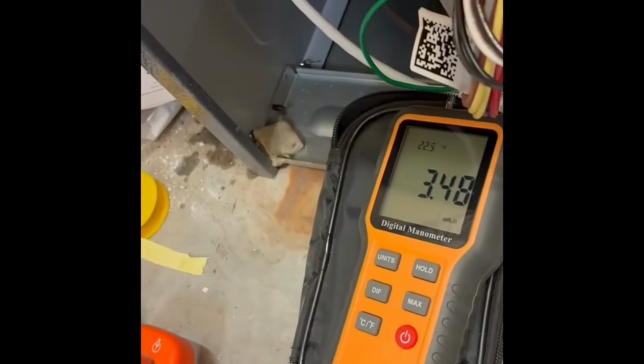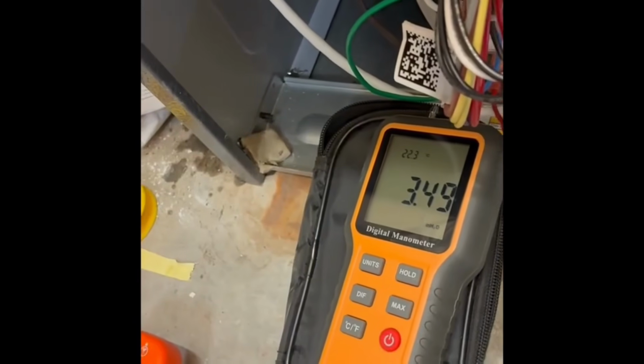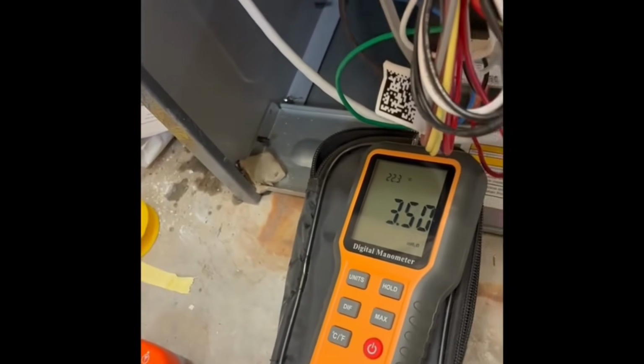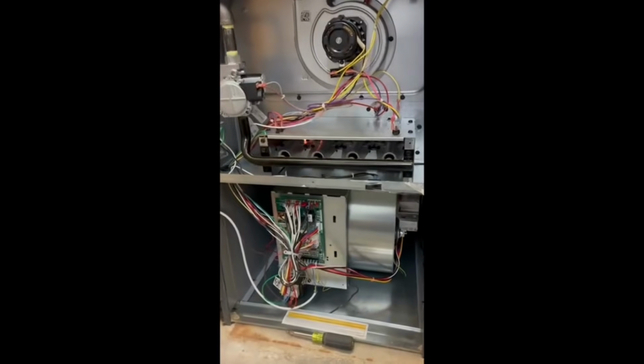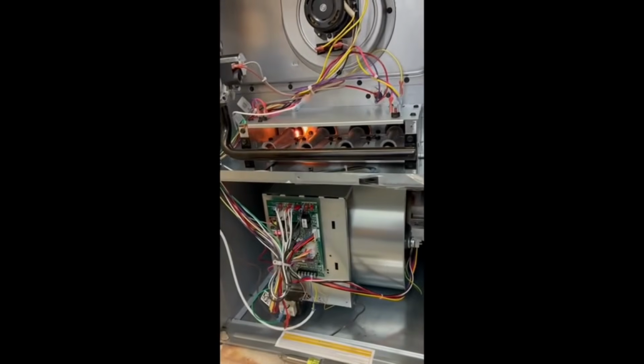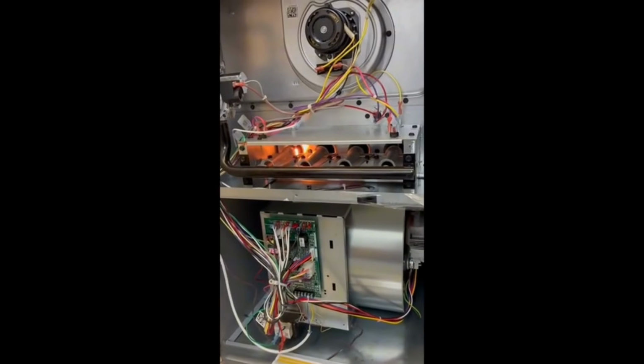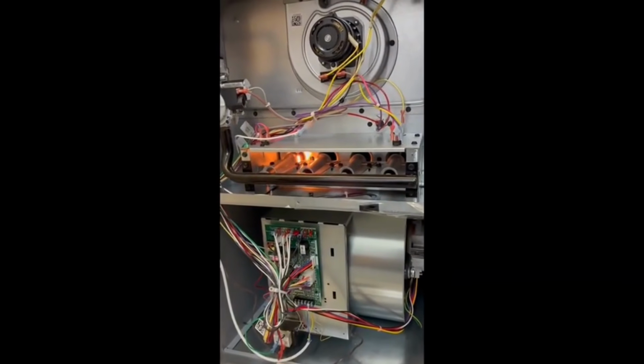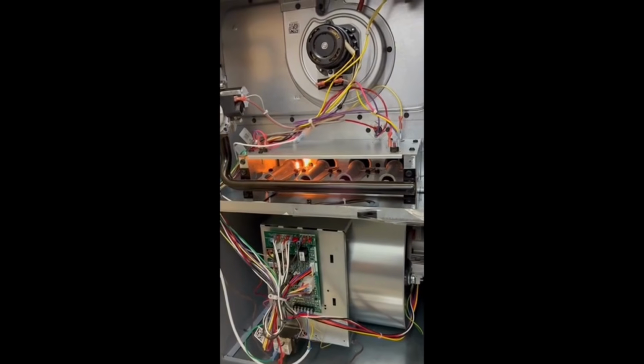And see, that was a little bit too low. I'll show you what I'm doing. Just going to turn it back to the right a little bit. Just about there. There we go. Now double check it again. And make sure you close those Allen ports, those test ports on that gas valve. That's important, obviously.